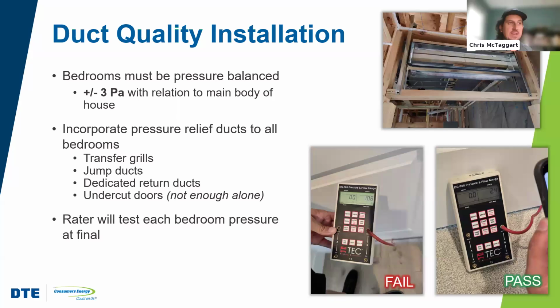And then the bedroom itself can actually act as a form of pressure resistance on the system when we're calculating our total system airflow. So for that reason, bedrooms have to have some method of pressure relief so that the supply air, because pretty much all bedrooms are going to have supply air, has a way to make its way back to a return. That can be done through either a dedicated return in bedrooms that's balanced with the supply air coming in, or transfer grills, jumper ducts, or door undercuts. It says door undercuts aren't enough alone. That's not necessarily true.